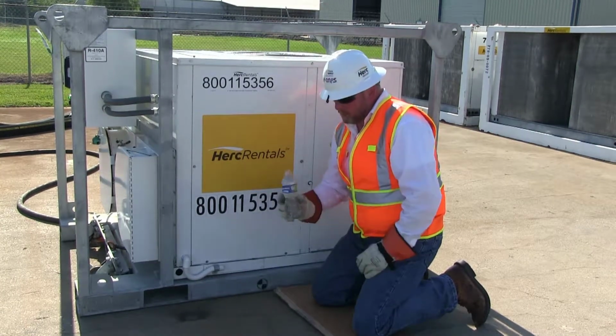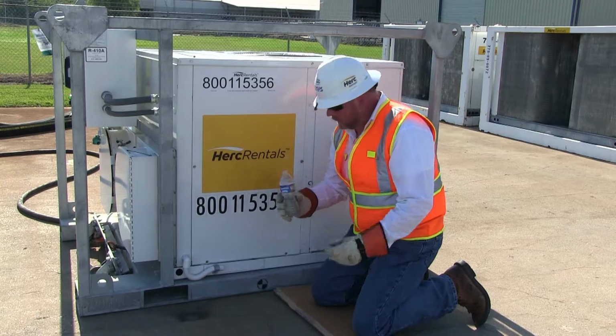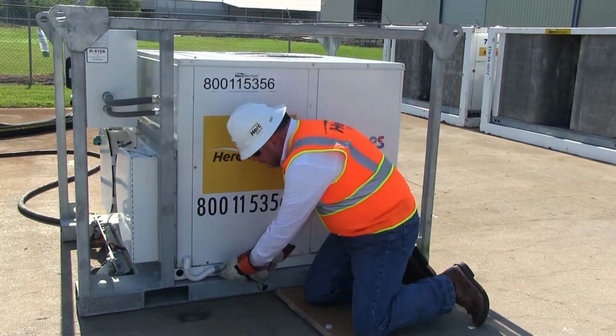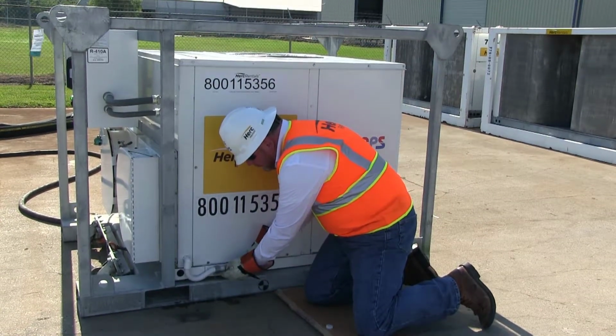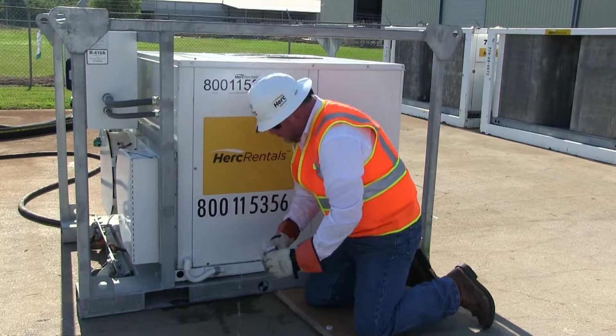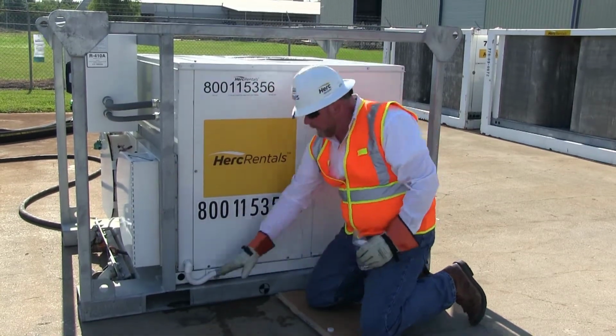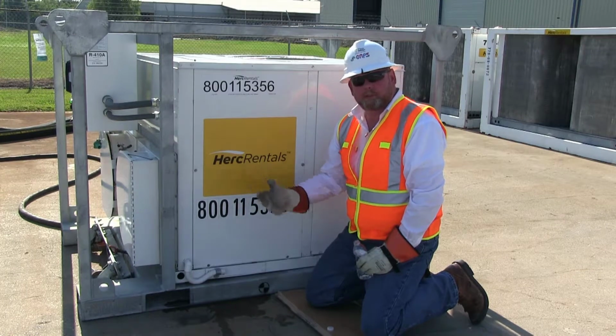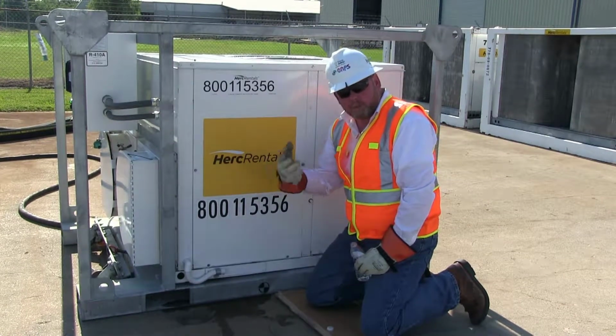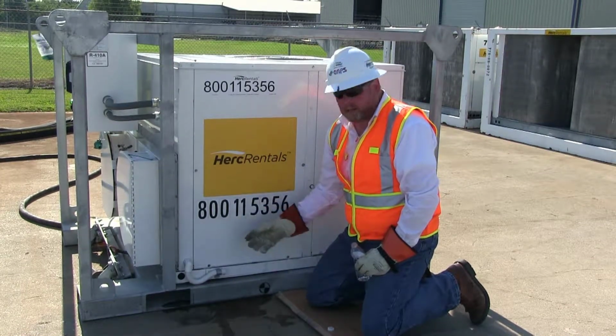So you're going to want to make sure that you take some water or water hose, and we're going to want to prime the trap. You just simply do that by putting a bottle here and filling the trap up with water. There's plenty of it came out. That'll create an air seal for us here so that when the machine comes up and operates and starts producing water, it'll freely drain and not be pulling the air back into the cabinet.